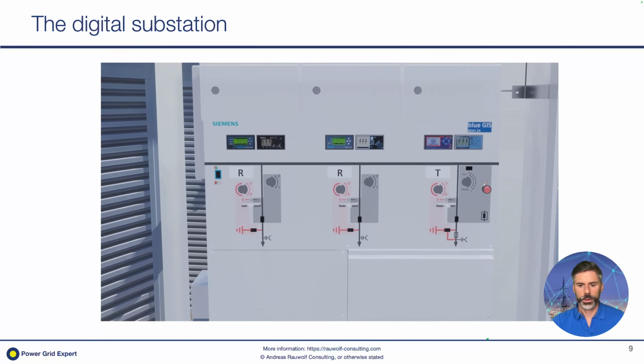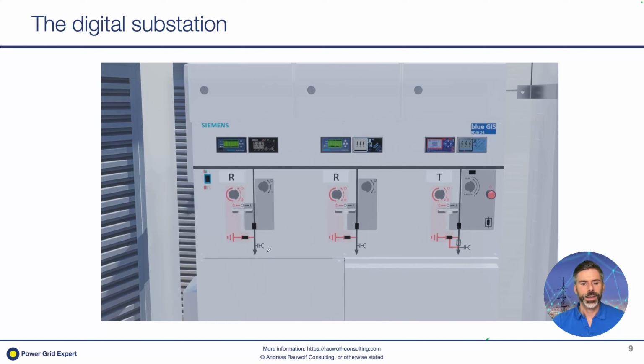The medium voltage switchgear is thankfully already putting the rough structure of the switchgear on the top, on the front panel. So we have, for example, incoming feeder, we have the outgoing feeder, and we have the transformer feeder. So that transformer feeder here is going to the transformer, and then we have here the low voltage feeders we just saw on the right side. In the medium voltage switchgear, as the name might suggest, we have switches, load breakers, power circuit breakers, depending on the application, earthing, of course, and we have those guys here.